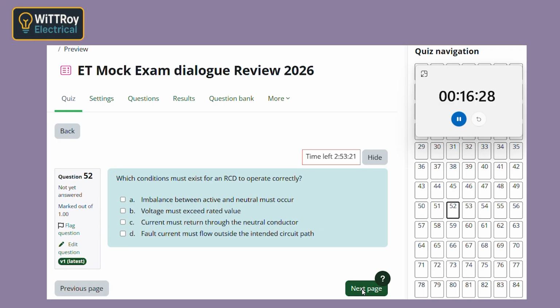Question 52. What conditions must exist for an RCD to operate correctly? Current must return through neutral, and there must be imbalance? Yes, let's explain that carefully. The RCD monitors the active and neutral conductors passing through it. Under normal conditions, the current leaving and returning are equal. So it's really comparing those two currents.